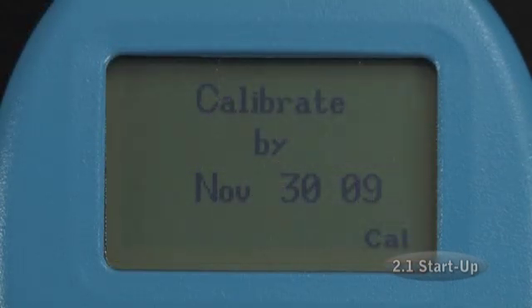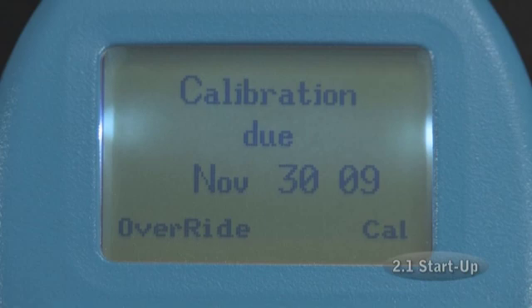After the pump test, the screen will show "Calibrate" by some date, typically 30 days from the last calibration. If the 30 days have passed, you can still use the instrument by pressing "Override." Alternatively, you can initiate calibration by pressing the right button marked "CAL" on the display.